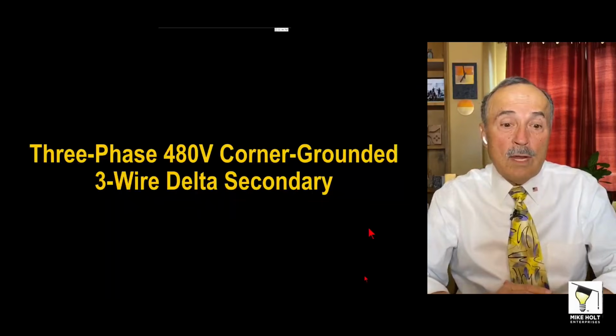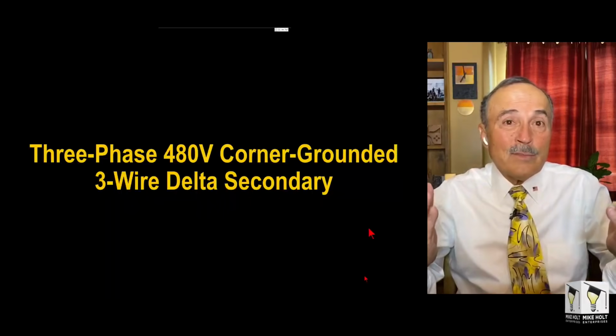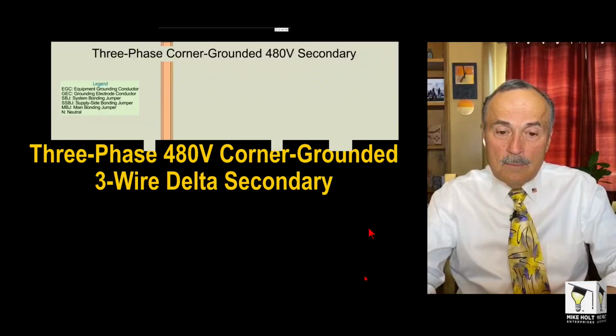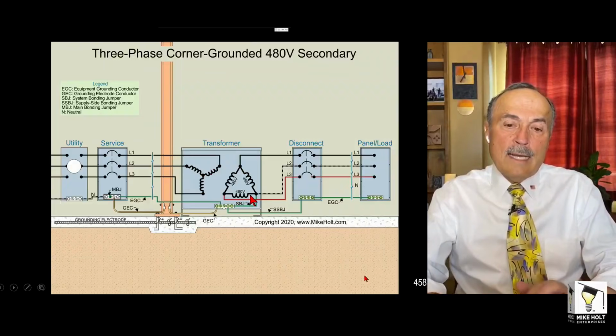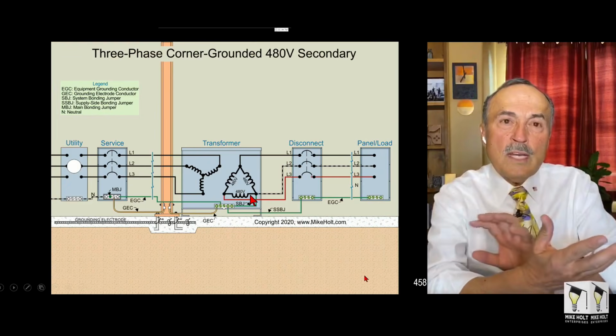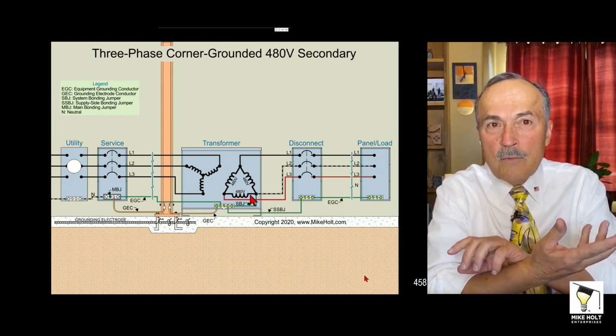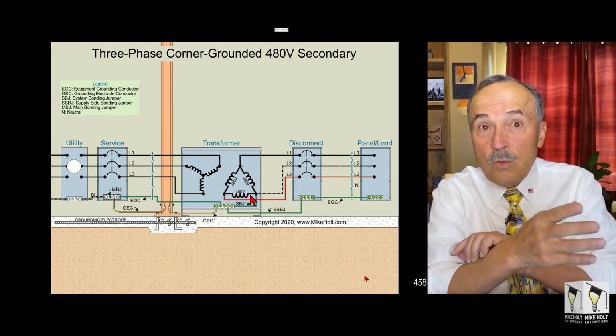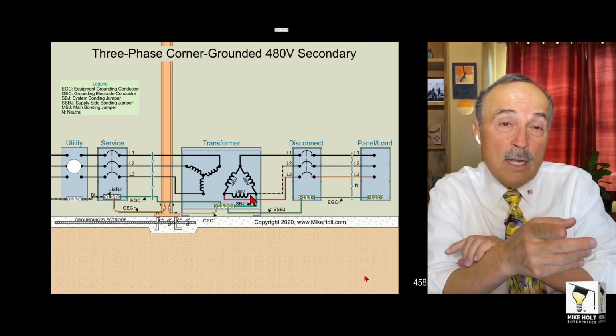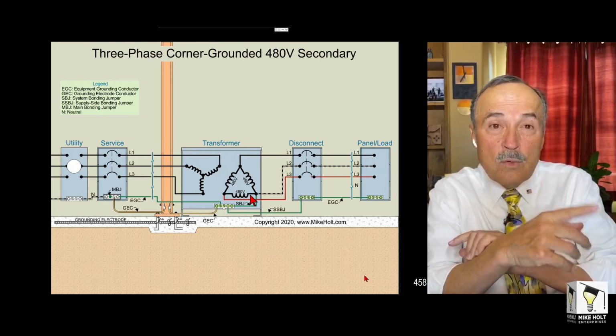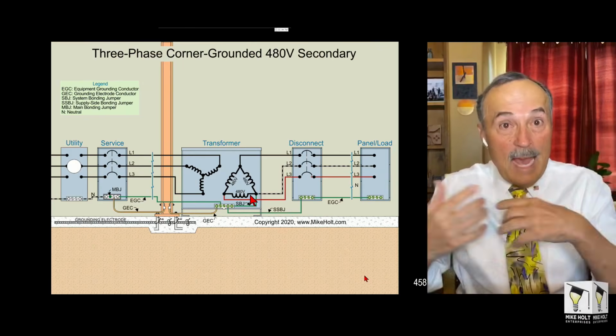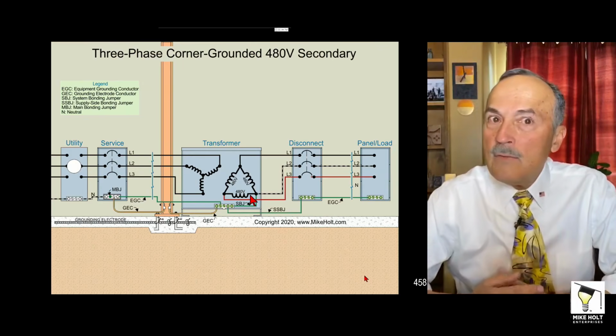That was it, I had on the corner grounded delta system. 3-phase, 4-wire corner grounded delta system. I'm showing a Y delta configuration where you reverse fed a transformer that was delta Y, where you were supplying 480 down to 120, 208, and you decide, you know what? If I get 480 down to 120, 208, I need 480, and I have a 120, 208, can't I just backfeed that little puppy right there?